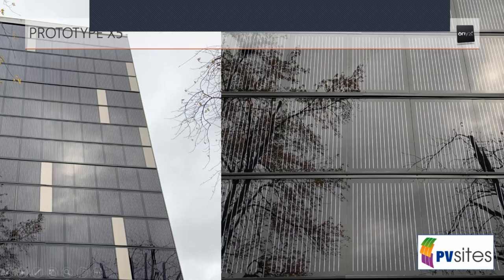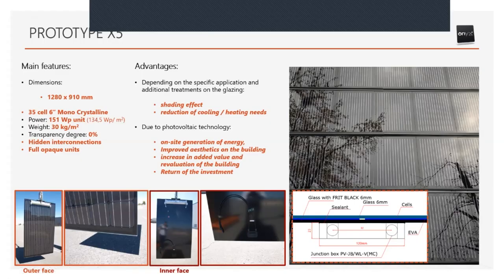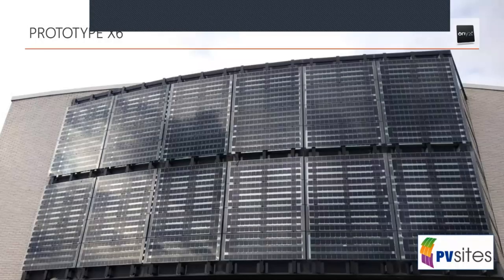From the France demo site, we developed the prototype X5, a double laminated PV glass whose main innovation is the hiding of all interconnection of the module, together with the use of a black rear glass that harmonizes the aesthetics. For the LEDMO site located in Spain, we developed the prototype X6, which is also a double laminated glass, but in this case we use crystalline back contact solar cells that hide the interconnections of the module. The design balances the power and the transparency as a result of its application as an exterior cladding on the system windows of the building.